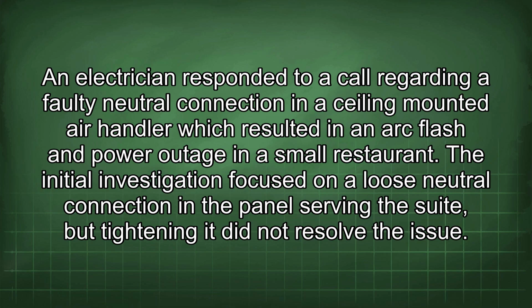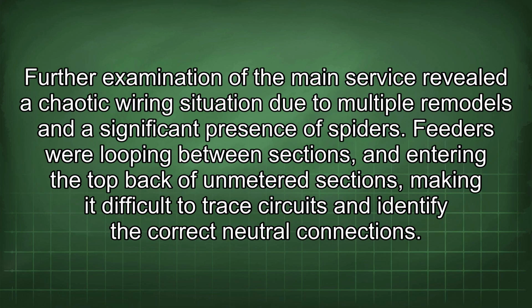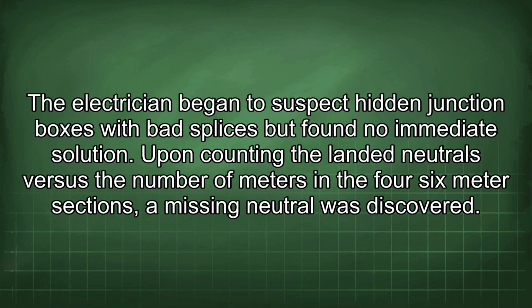Further examination of the main service revealed a chaotic wiring situation due to multiple remodels and a significant presence of spiders. Feeders were looping between sections and entering the top back of unmetered sections, making it difficult to trace circuits and identify the correct neutral connections. The electrician began to suspect hidden junction boxes with bad splices, but found no immediate solution.